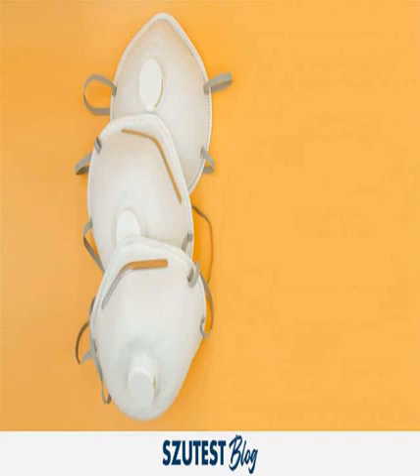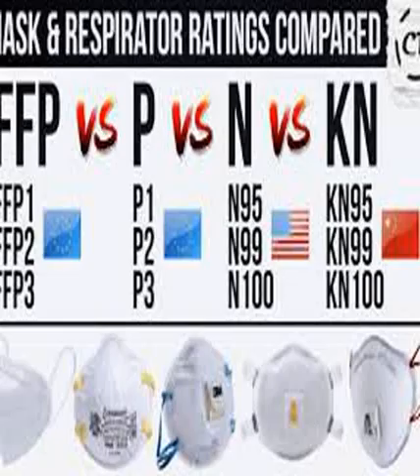EN 149 defines laboratory tests, field tests and certain requirements to ensure the conformity of the masks. The following points are analyzed. There are some European organizations that issue an examination certificate confirming conformity and specifying the characteristics of the products. With the publication of the 2009 version of the standard, the designation of the respiratory protection mask is now particulate filtering half mask. The abbreviation NR or R is added after FFP1, FFP2, FFP3. Additional suffixes include D. Masks manufactured before the new standard was taken into account may still have the old marking.